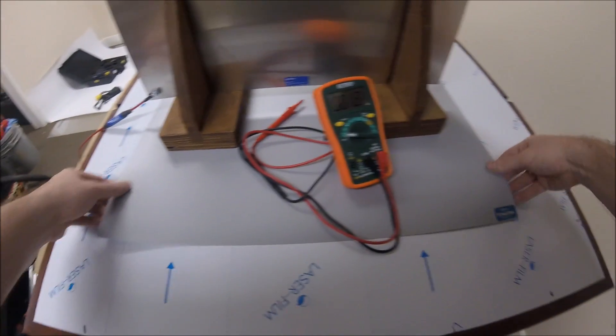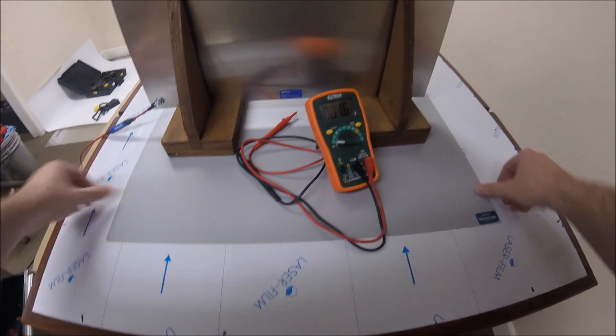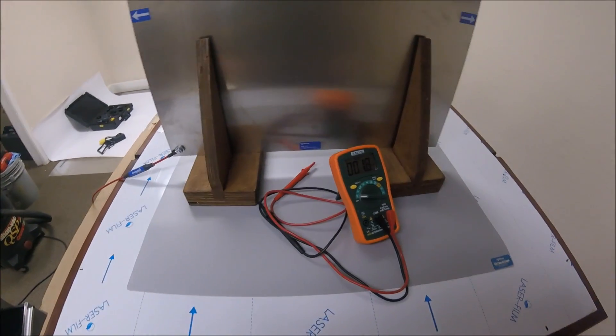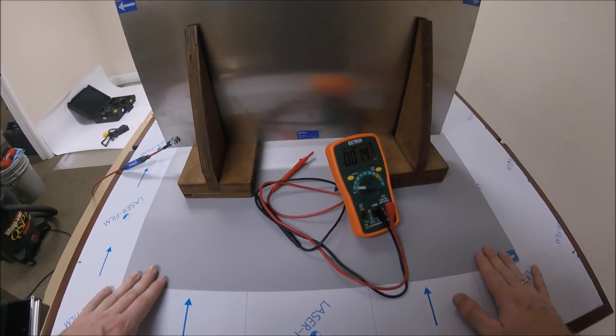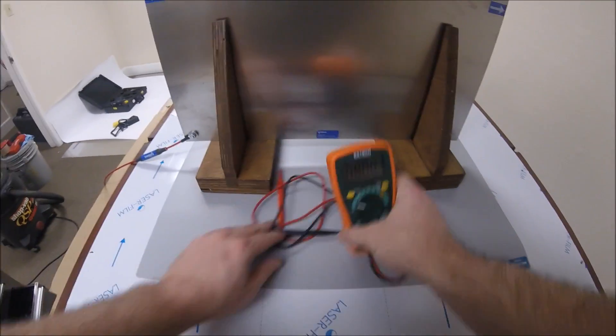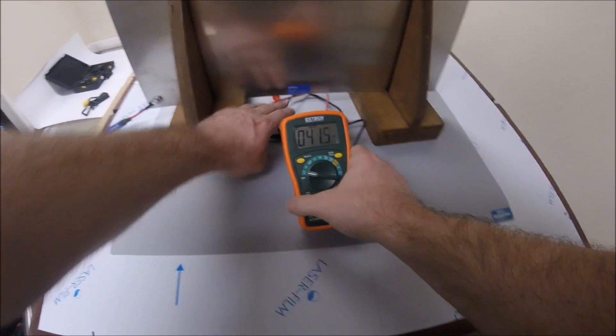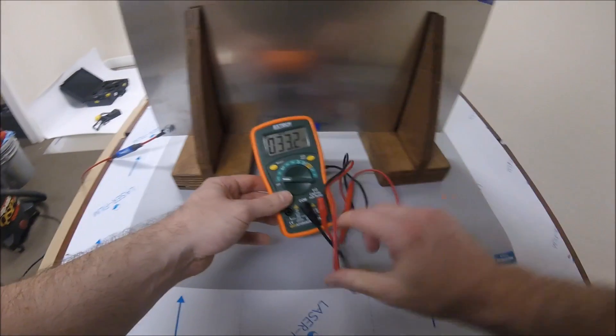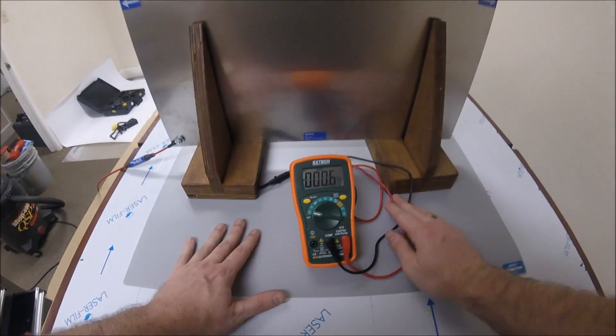If you're wondering about the setup, I have a table top from the ESD environments we manufacture with a horizontal coupling plane built in. It was manufactured recently, and you'll notice we were working on the top of a thin layer of protective film. I'm moving an insulation foil here to better represent the standard.